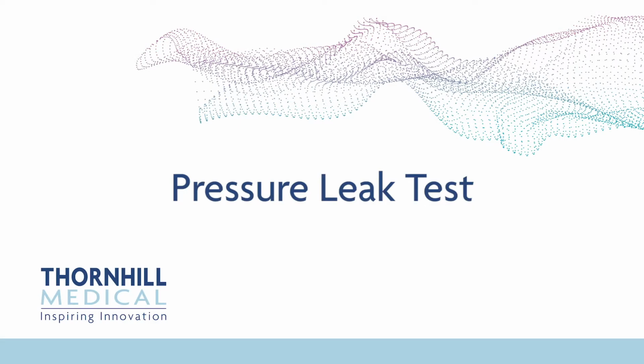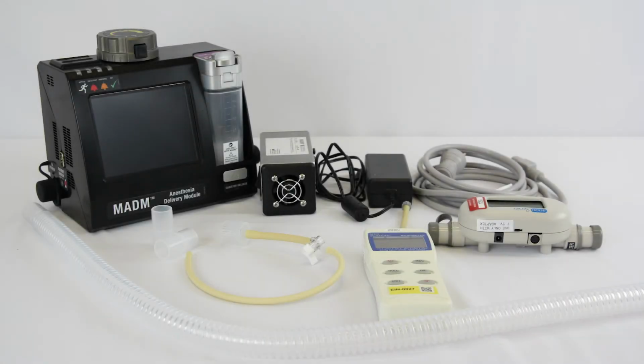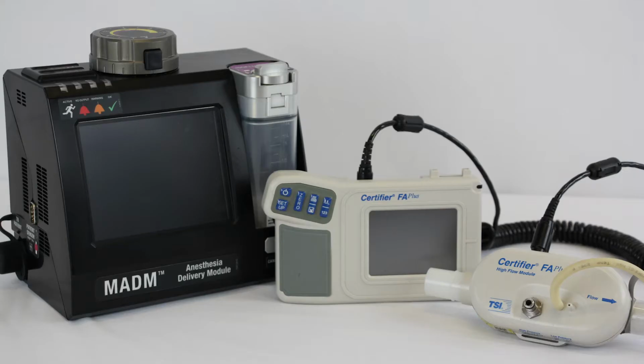Pressure leak test. For the pressure leak test, you will need an adjustable flow source, the power cable and adapter, patient sensor circuit adapters, a pressure leak test plug with tube, a pressure meter or a manometer, a flow meter, and patient tubing. Optionally, you may also use a ventilator analyzer such as the TSI Certifier Flow Analyzer for this test.